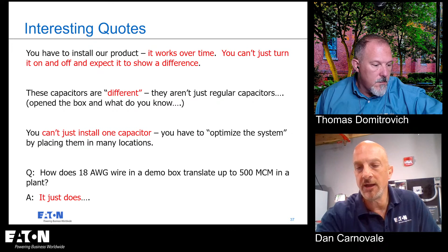So let me zoom this out. Here's your transformer, 500 kVA. You'd have 400 kilowatts, as we showed earlier, and 300 kVAR. So that's your 3, 4, 5 triangle. Your initial power factor would be 0.8, which is 400 over 500. That's your power factor.